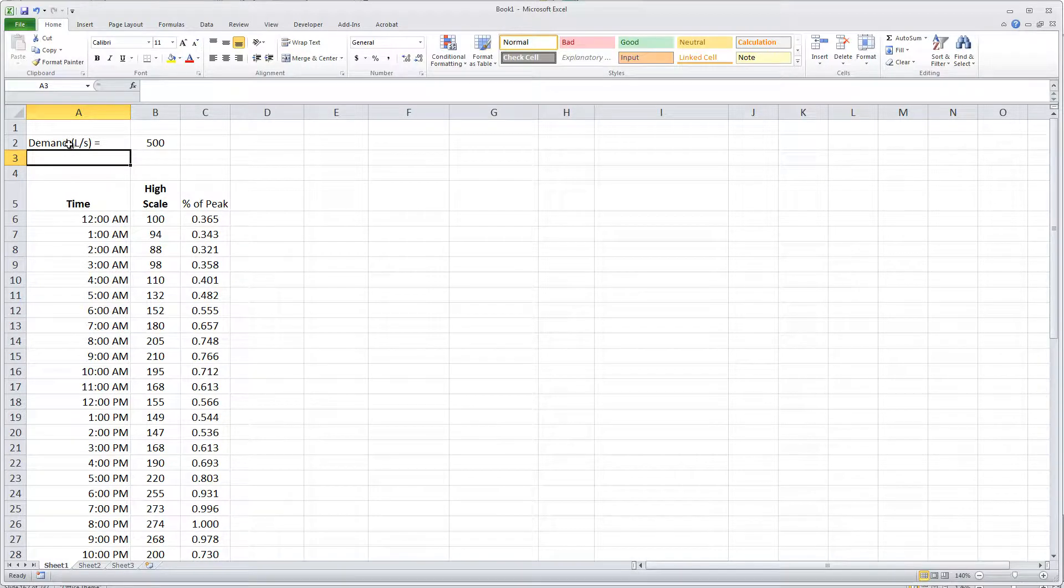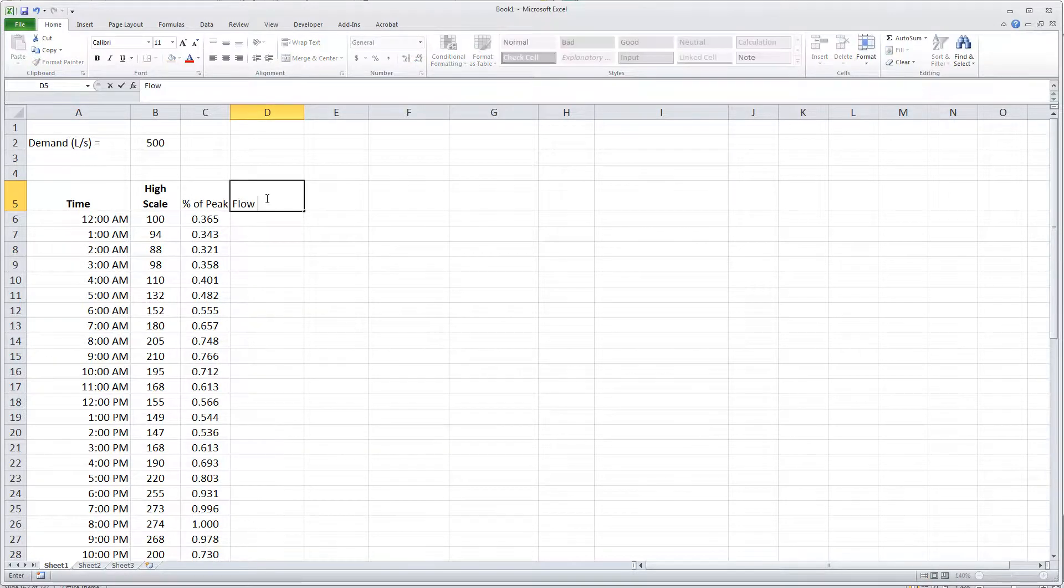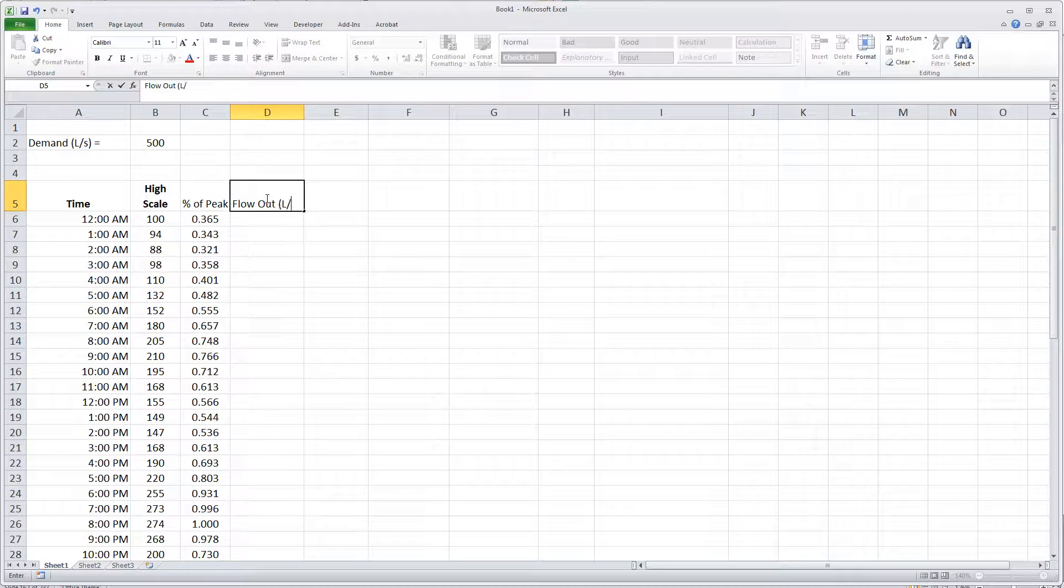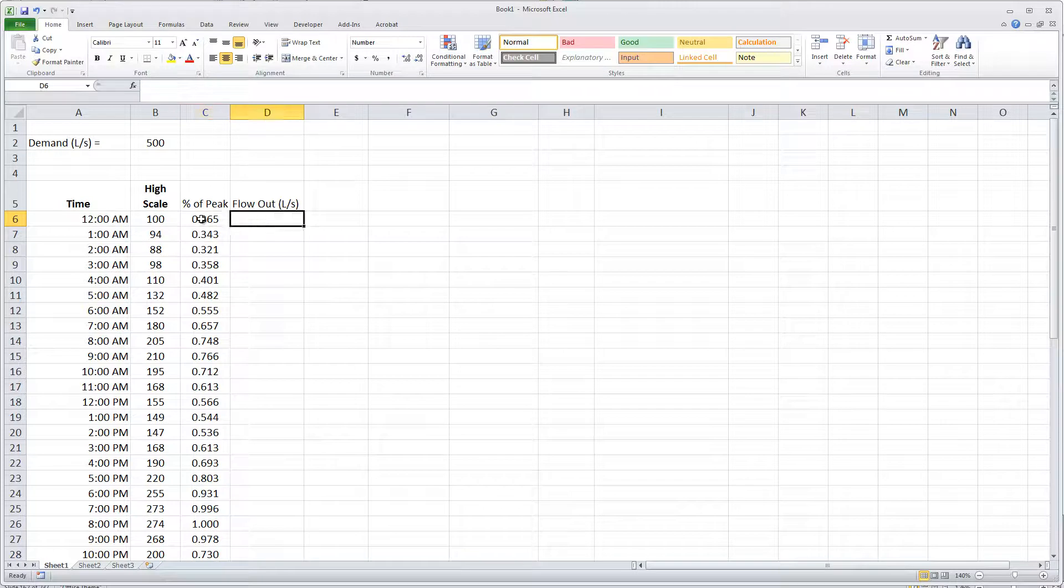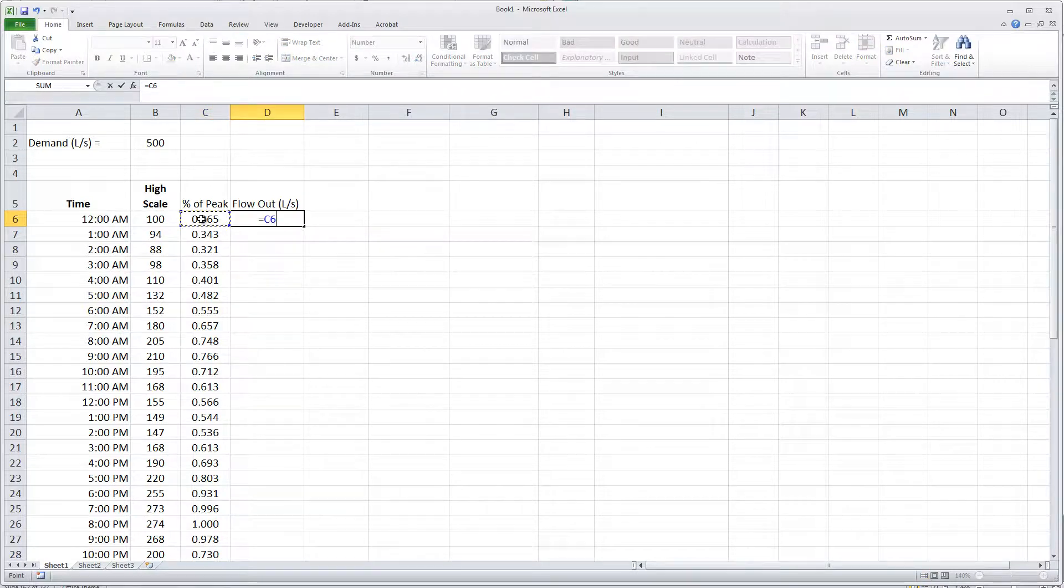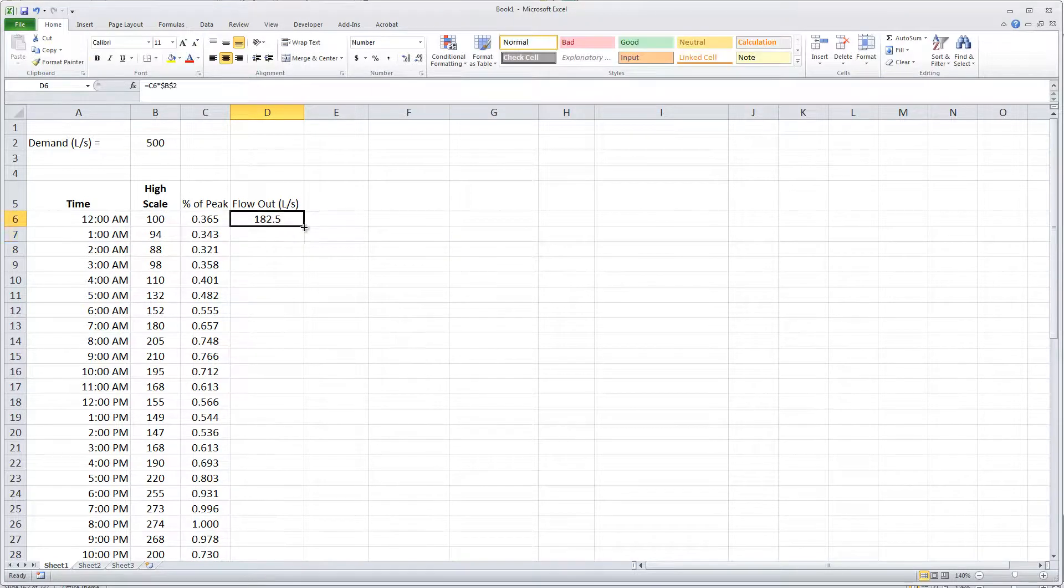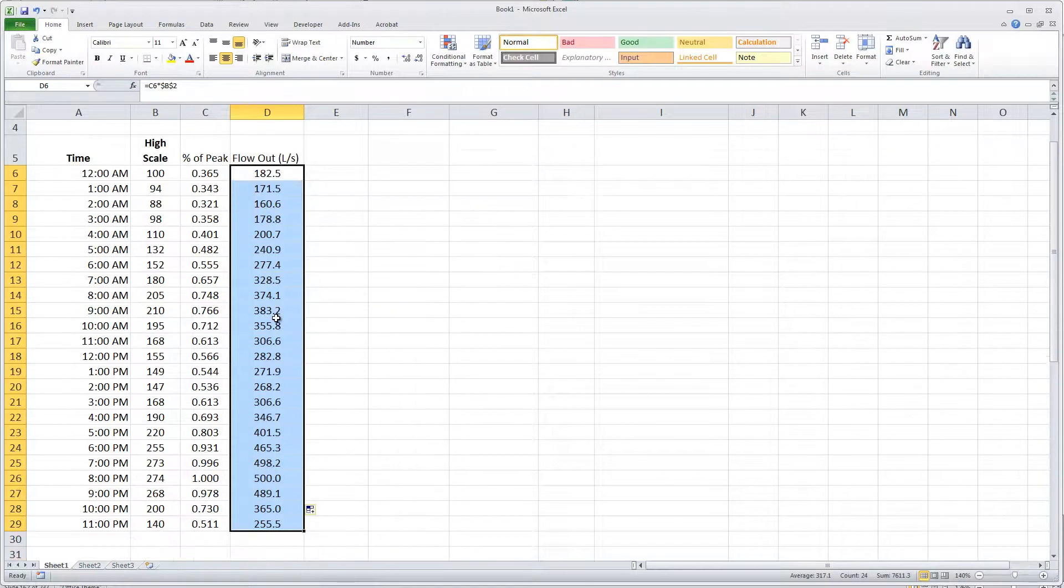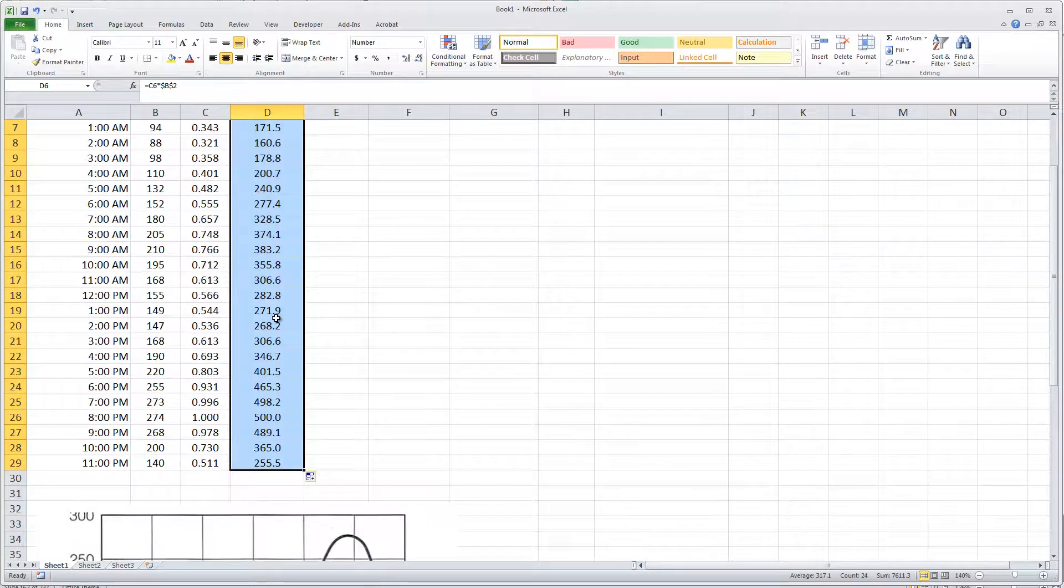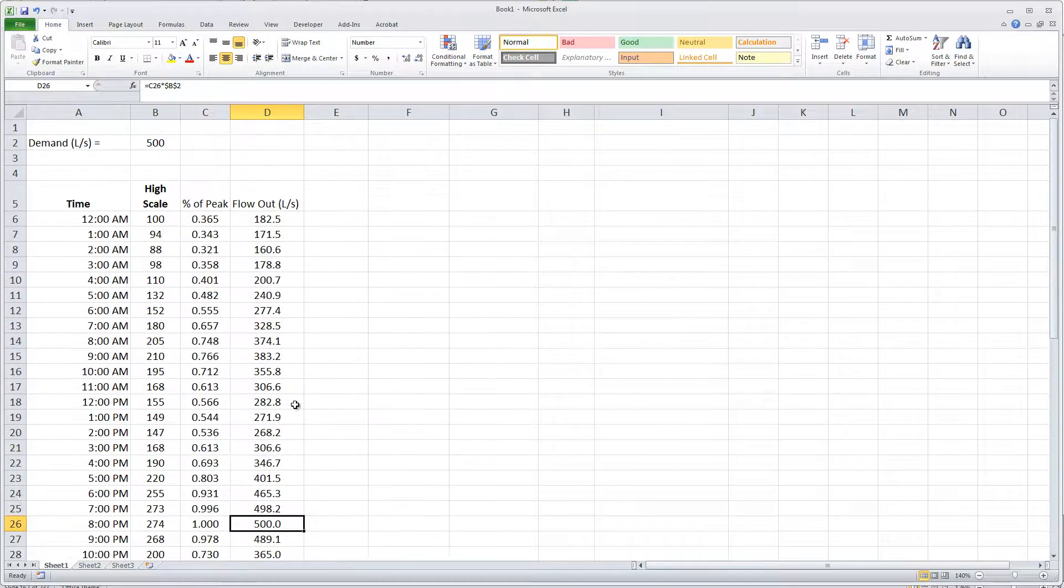So what I want to have now is the flow out for each hour, flow out of the reservoir in terms of liters per second. The flow out is going to be this peak flow rate times the demand, and I'm anchoring the demand by pressing the F4 key. If I double click this through, I can see at every hour of the day what the flow out of the reservoir is. At the eight o'clock hour, the flow out of the reservoir is 500 liters per second.